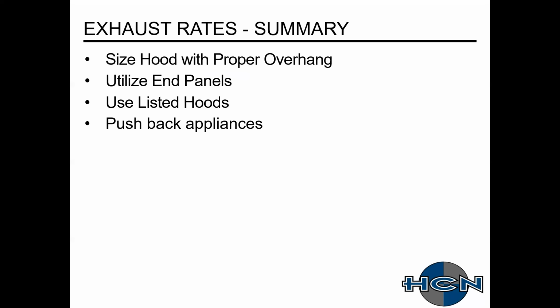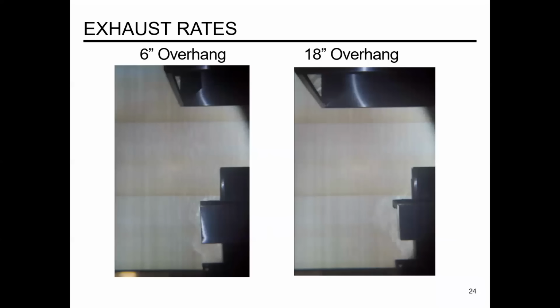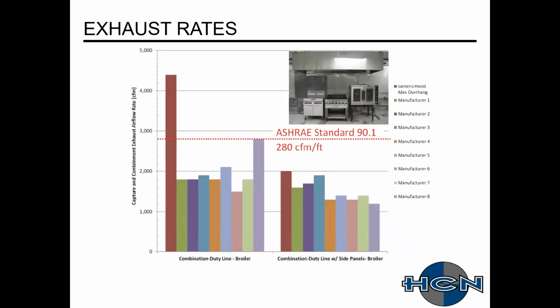So to summarize what we went over on this portion of the presentation, for exhaust rates, the big thing you want to do is size that hood appropriately for the equipment you're covering, and have the proper overhang. For wall canopy hoods and back shelf hoods, we really have to be utilizing end panels. And another thing that I didn't talk too much about is pushing those appliances back. In that mixed flow, typically you'll have these fryers pushed forward so that they're the same distance across, because cooks like to walk down the line. The problem with that is you're going to get a lot of airflow that comes in underneath the equipment and comes back, because that hood's basically a big vacuum. It's pulling from everywhere. So if we can seal off that back end, it's going to improve your capture as well. Pushing appliances back is usually a pretty quick, easy way to solve some problems.